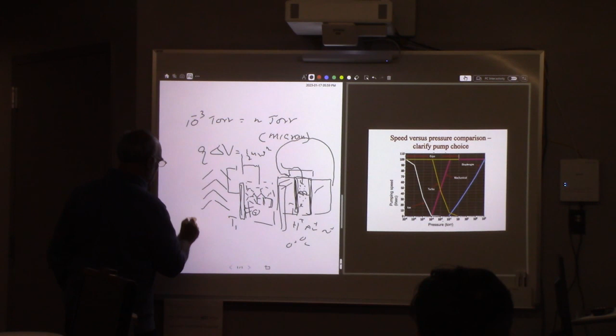Now if you get to low pressures, turbo pumps and ion pumps don't work at these higher ones, because typically we start these pumps after we rough the vacuum. So up to here we don't even start these pumps - only here, even the cryo pump. So the cryo pump also we don't start until we get to this low pressure.